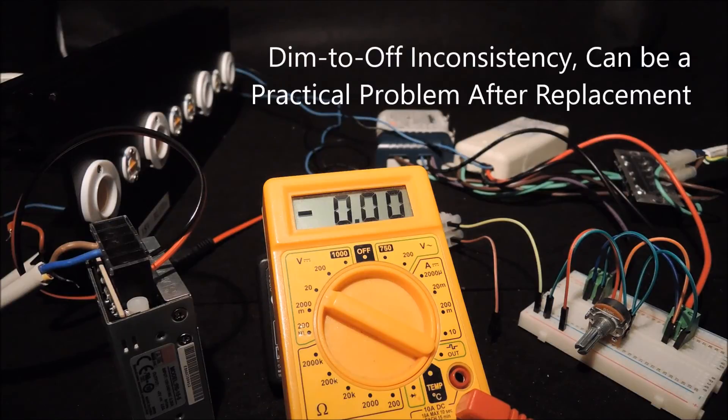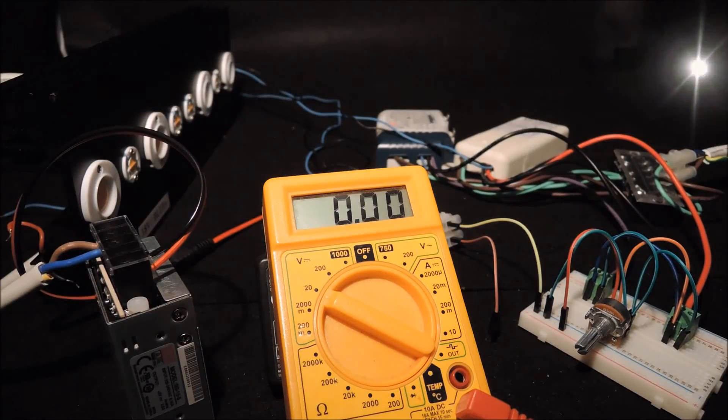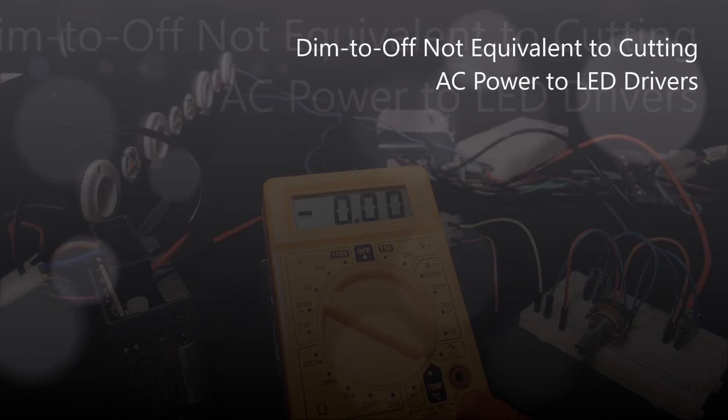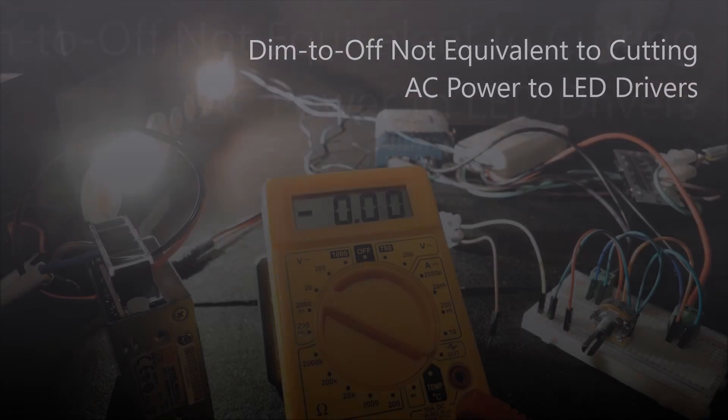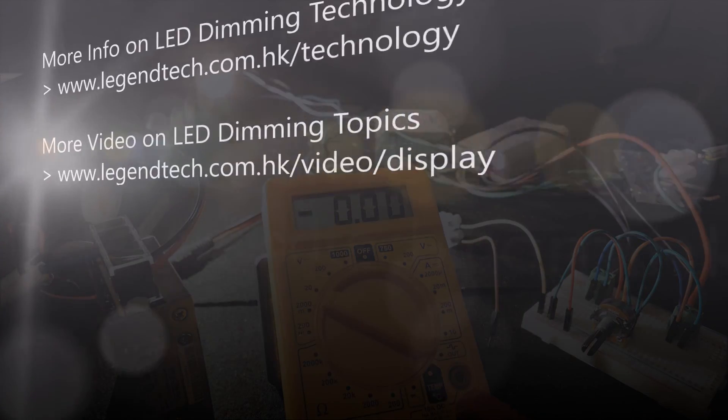Last but not least, we must remind that when there is no light output, the power that connects to the drivers would actually show a non-zero reading. Again, the dim to off feature is not equivalent to actually cutting off the AC power to the driver.